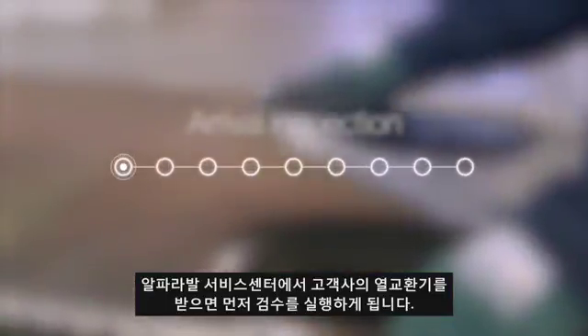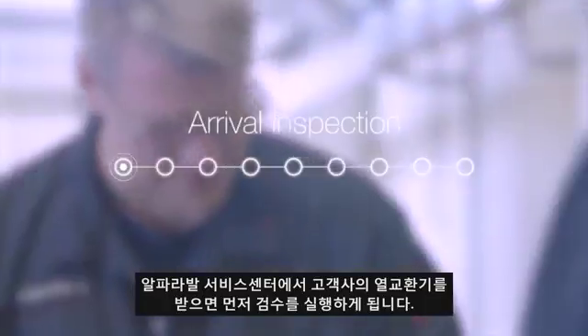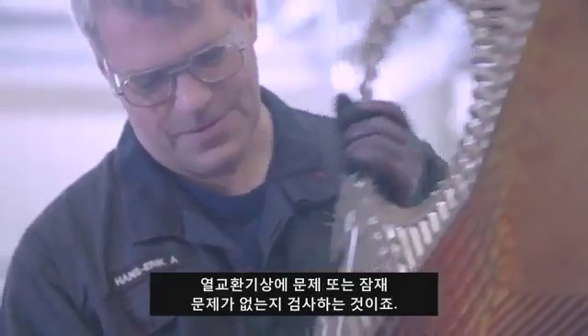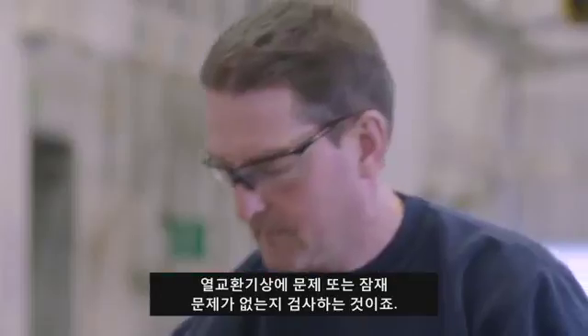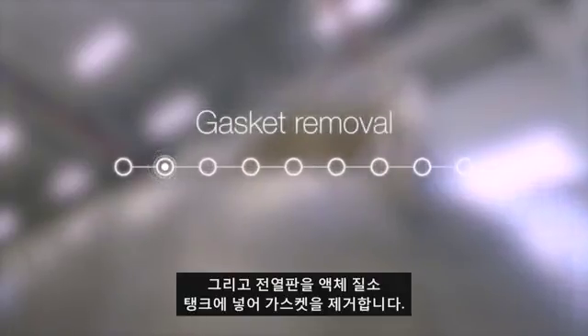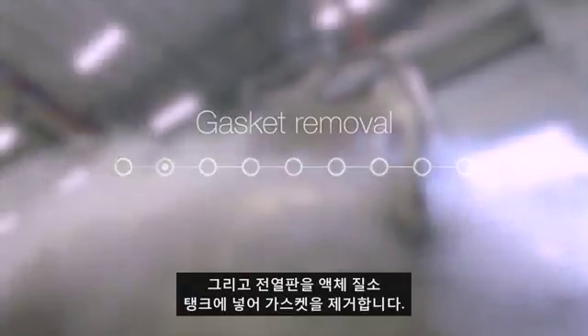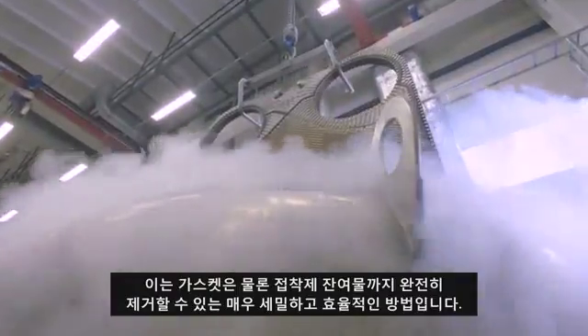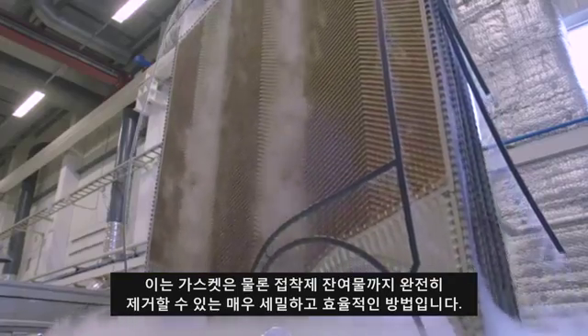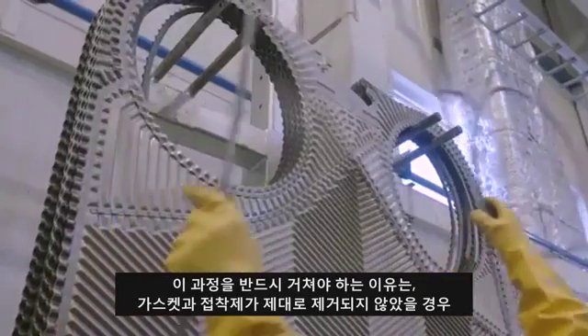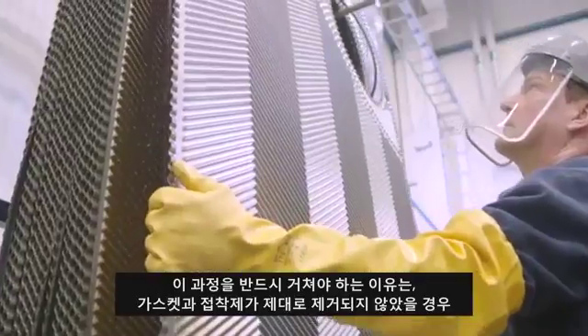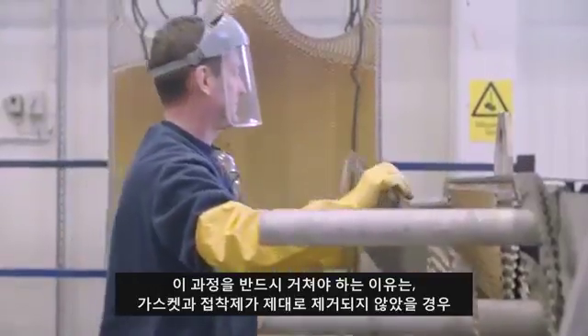The first thing we do when we receive the heat exchanger is arrival inspection. And here we're looking for any present or emerging problems with the heat exchanger. We remove the gaskets by submerging the plates in a liquid nitrogen bath. And this is a very gentle and efficient way of removing all the gaskets and the glue residues. And you want to do that because if you don't get all of that away, you might face problems sealing the unit later on.